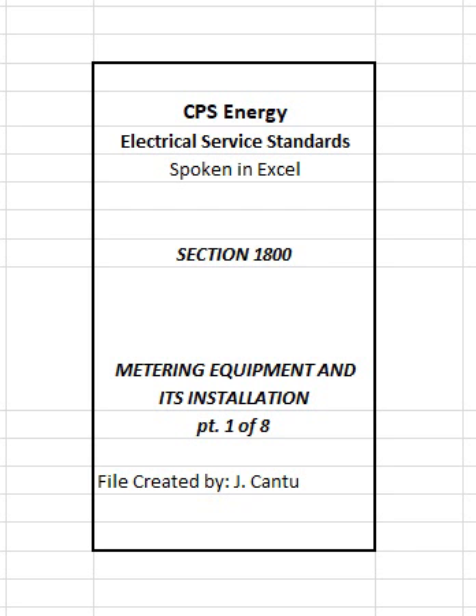B. Conductor size limitations. Conductor sizes permitted in self-contained meter sockets shall be as outlined in Figures 1801 and 1802 where customer is responsible for furnishing and installing both line and load conductors within a meter socket. Conductors shall be sized the same and must be of the same material and ampacity rating.